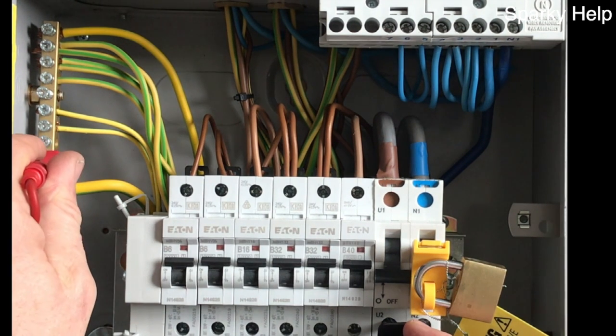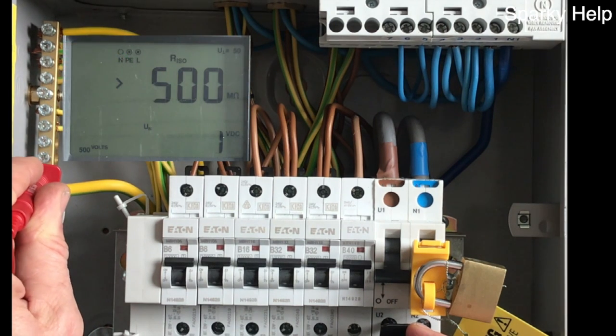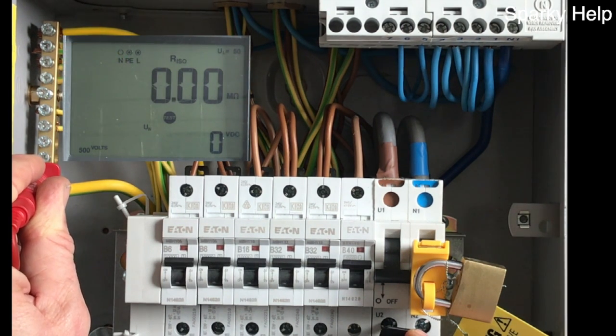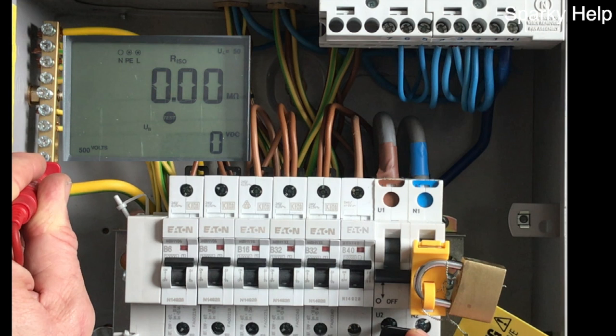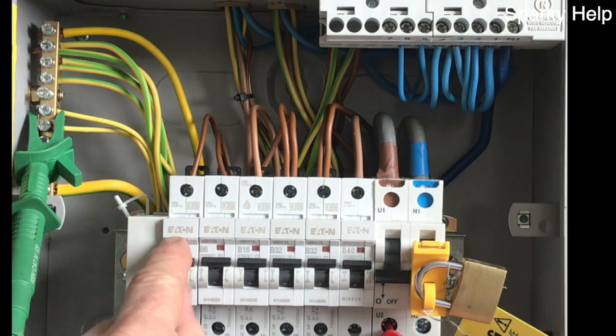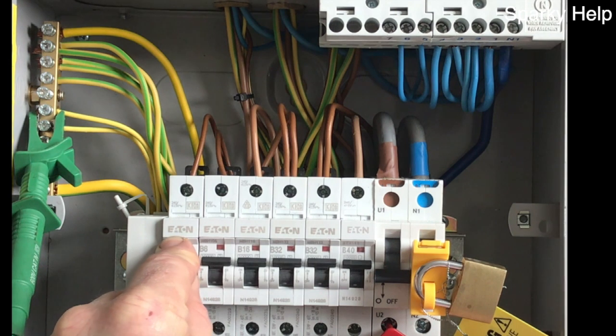So here's another fault. This time the fault is found to be between line and earth. So we can test every single circuit to earth, to the earthing system. So short circuit line to earth. And same procedure, turn each breaker off or turn them on, whichever is your preference.